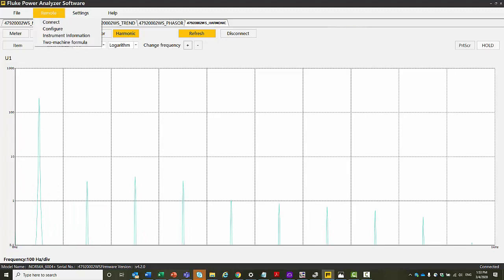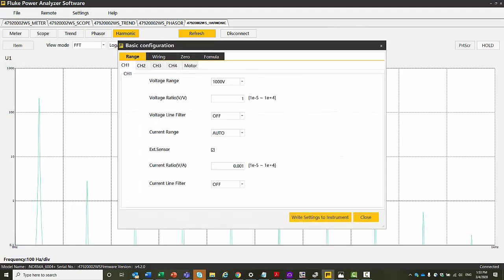When it comes to setup, we can go to the configuration, and here are all the settings that we have inside the instrument. So we do this per channel. So we have per channel 1 voltage range, ratio we can input here. We can put in whether we have a voltage line filter, 650 Hz or 10 kilohertz. That depends on the kinds of measurements you're making. You've got the current line filter as well. You can go to each of the channels independently. So for example, if you have 3 ACs and a DC, you can do that.